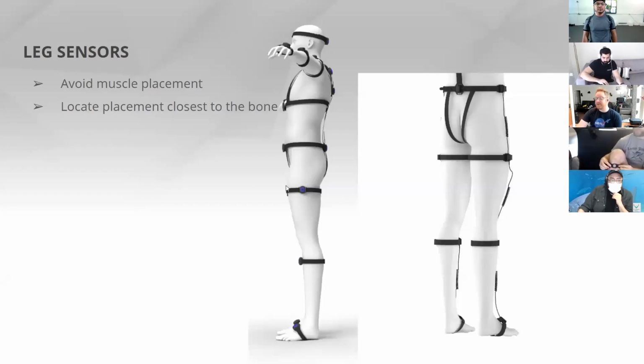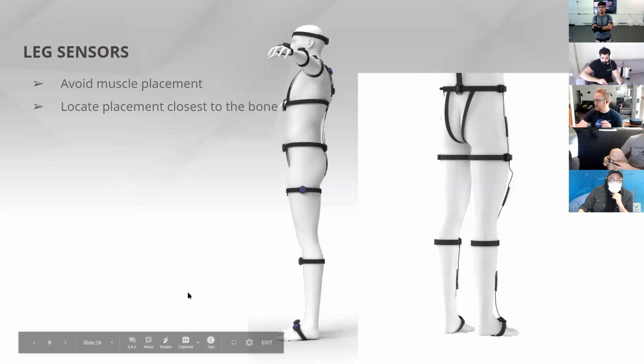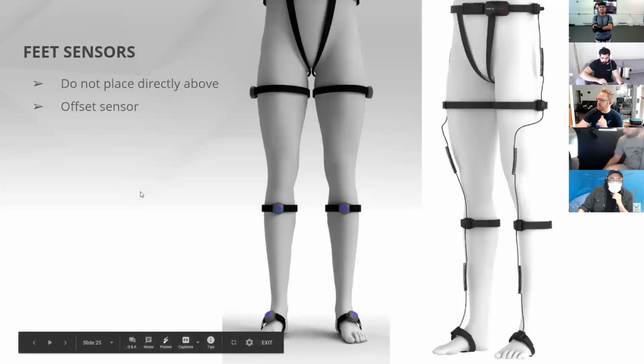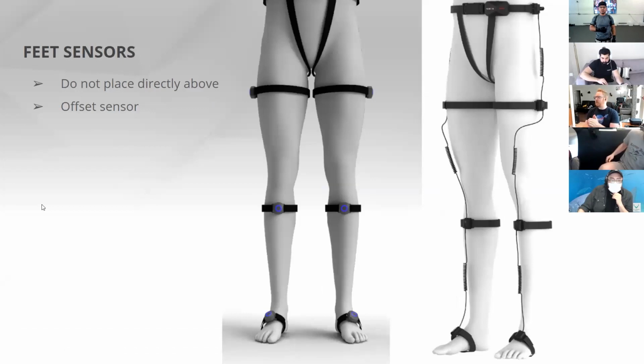All right, so leg sensor, thighs 90 degrees out, shins facing forward, slightly inwards. And with the feet, you want them on the flat part of the outside of the foot. So again, this is the same issue. If you place the sensor on the very top of the foot where that arc is, you're gonna get some wobble. If you cock them out just a little bit so they're on the flat side of the foot, you're gonna get a nice, solid, stable connection.